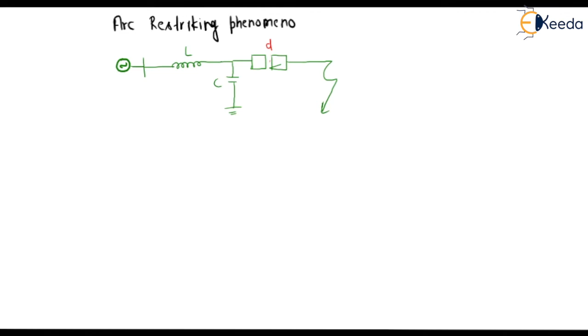So the first time we quench the arc, there is a distance between the contacts, and the primary arc is interrupted. So basically the voltage across this contact of the circuit breaker, VA, will be equal to the value of VC. But during the first arc interruption, all the current will flow from here. So when this is open, all the current will flow from here, and you can see clearly that it will form an oscillating circuit.